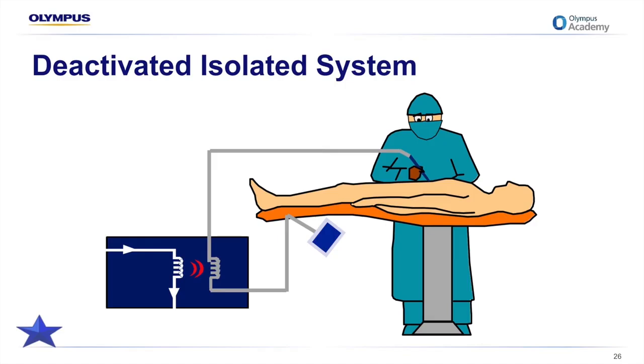The only way to complete the isolated circuit is through the patient return electrode. This safety feature has virtually eliminated the concerns regarding alternate site burns. However, it doesn't prevent a burn under the patient return electrode. And now I'll give you a demonstration of what I mean by that.